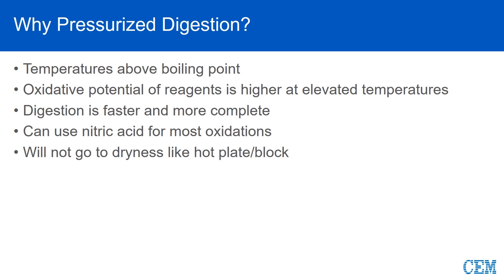Pressurized digestion allows one to heat acids above the boiling point. This increases the oxidation potential of certain acids like nitric as well as increasing the solubility of the solution. Think of how hot water will dissolve more than cold water. The digestion process also goes much faster and provides a more complete digestion compared to hot blocks.